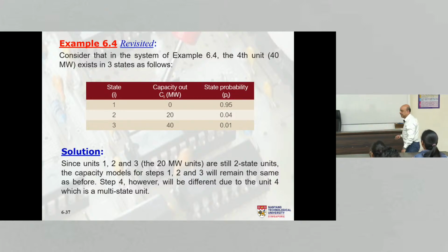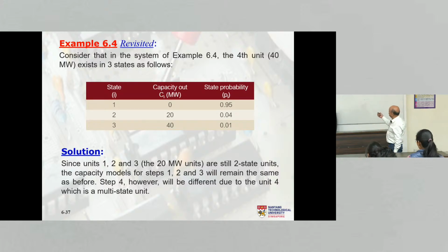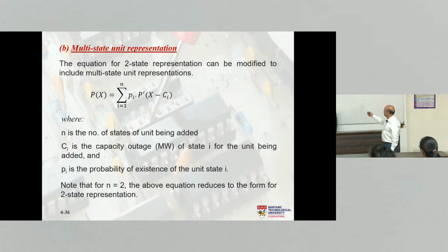So in order to save us that time and effort, I'm not changing the first 3 generators from this example, but I'm changing the fourth generator, the 40 megawatt unit, and instead of the 40 megawatt generator existing in 2 states, now I'm saying that it can exist in 3 states. So the state is i, the capacity outage is Ci, and the probability of that capacity outage is Pi. Clear? Those are the things that we will need for this equation. Yeah, the small Pi, state probability, the small Ci, capacity of that particular state being out.